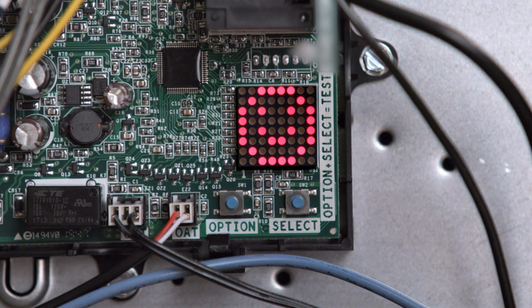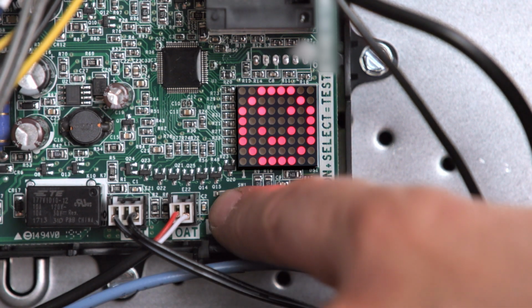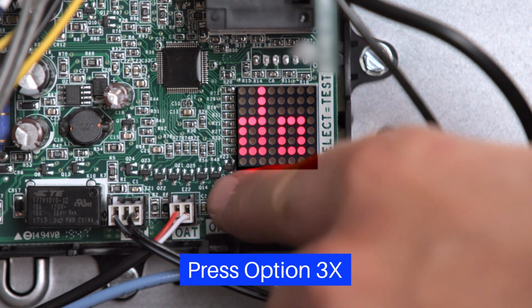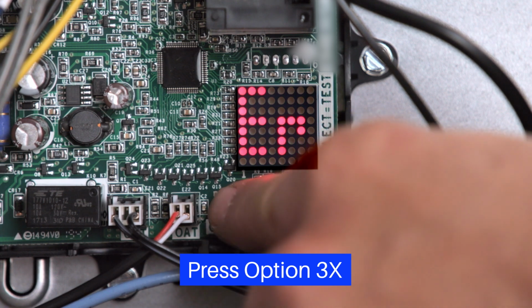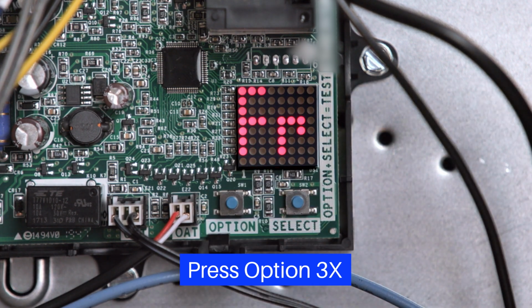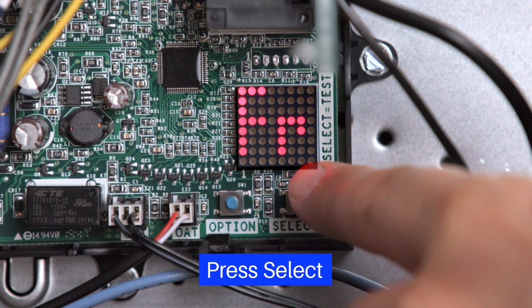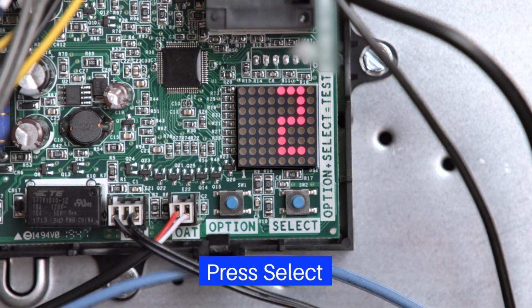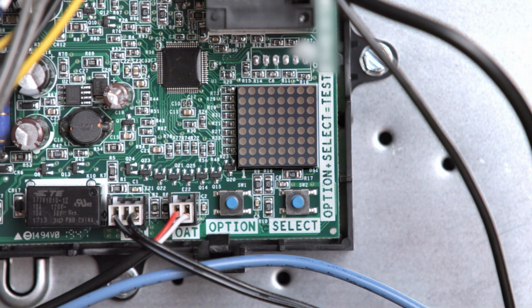Stored errors are fault conditions that can be recalled in the FR menu. To access the FR menu, press the Option button 3 times or until FR displays. Then press the Select button. The last 4 faults stored with a maximum of 2 identical faults will be displayed.